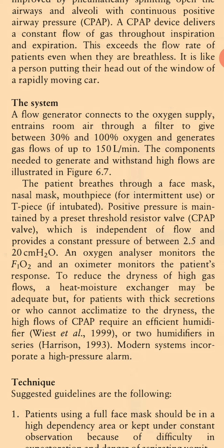To reduce the dryness of high gas flows, a heat moisture exchanger may be adequate, but for patients with thick secretions or who cannot acclimatize to the dryness, the high flows of CPAP require an efficient humidifier or two humidifiers in series. Modern systems incorporate a high pressure alarm.